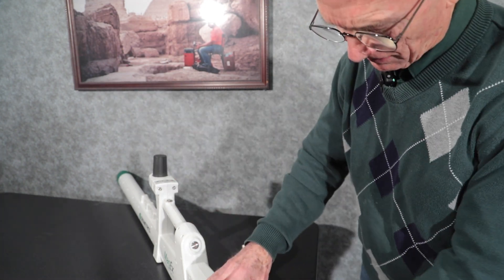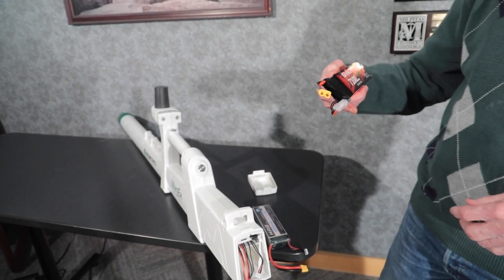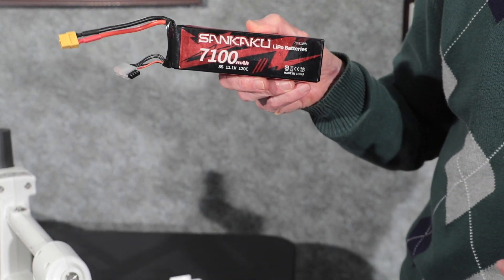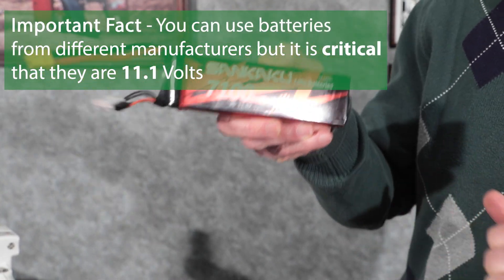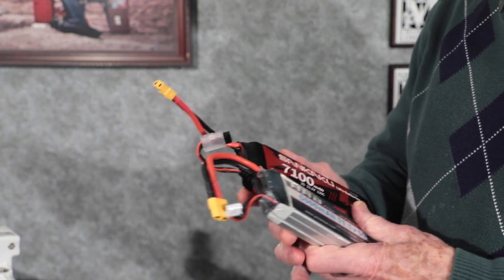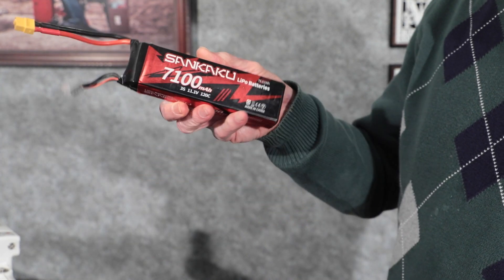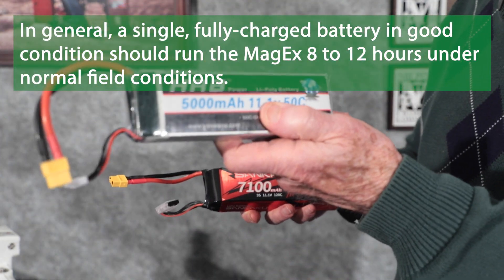We also happen to have another battery here. You can use two of the same, and it doesn't even have to be these particular brands. This one is a Sankaku 7,100 milliamp hour — 7.1 amp hours. The critical thing is the 11.1 volts. As long as that's met, the form factor can vary slightly; one is a little bit deeper than the other because it has a higher amp hour rating. This larger one will probably run the instrument for about 12 hours on a single battery, and the smaller one perhaps about eight hours.